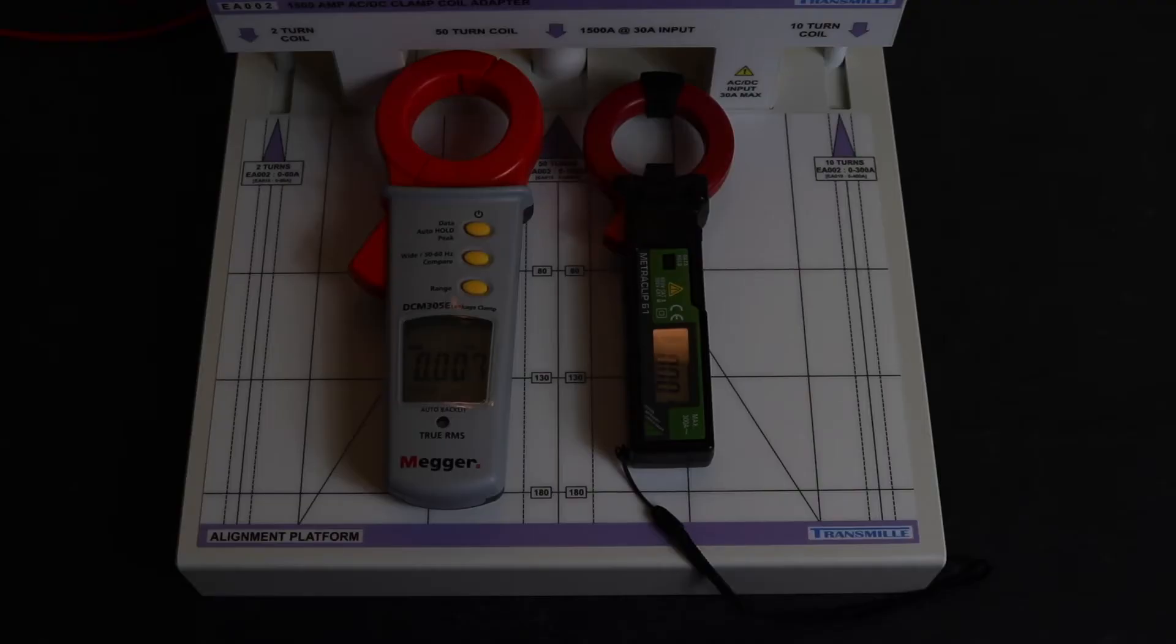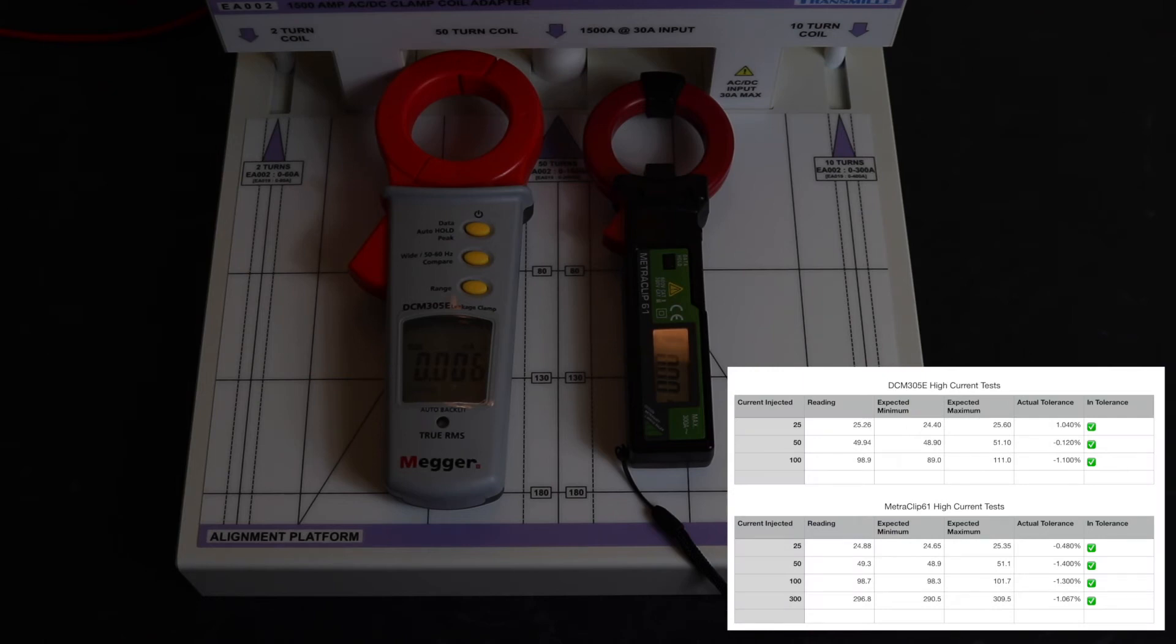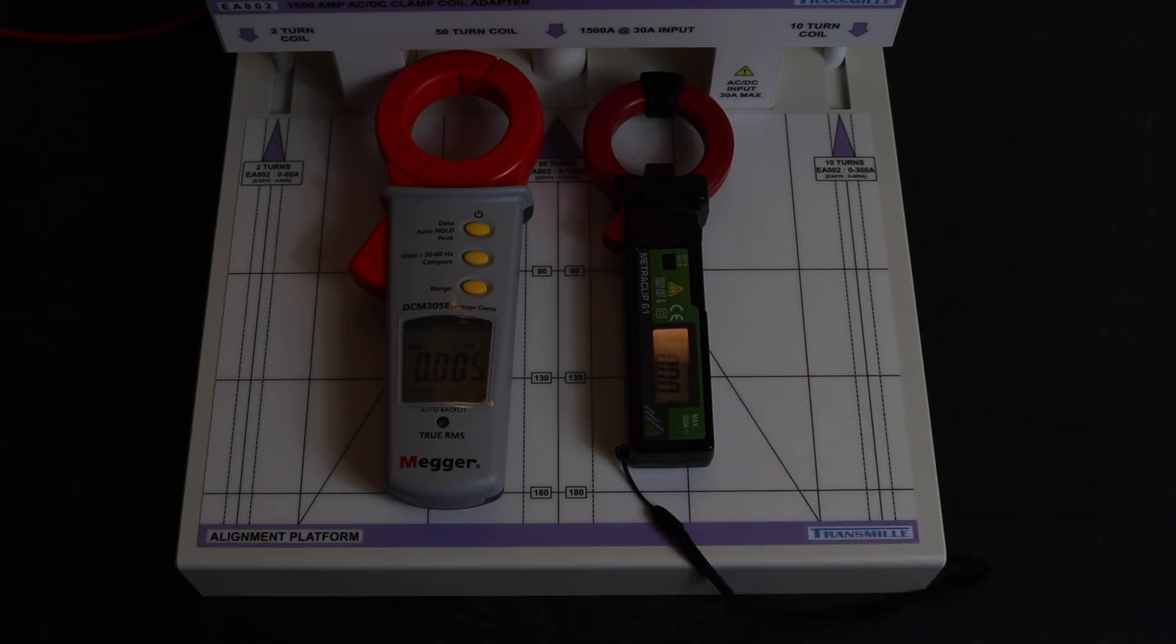Okay so results time for these high current readings that I made with these instruments and the cable clamp. And you can see I've got green ticks all the way down. Both instruments showing themselves to be in tolerance. So yeah quite happy with that test result there. So we'll move on to making some tests at some lower current settings.